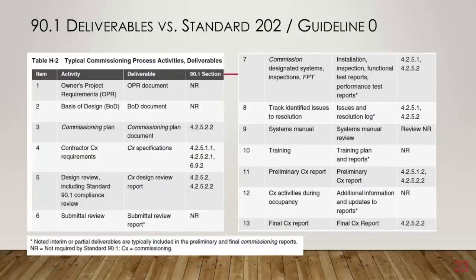Now this table is taken from the informative appendix. Again, what we did our best to do in that informative appendix is walk through, here's the standard process that Standard 202 lays out and indicate where 90.1 specifically requires those things and point to the actual sections in 90.1 where those requirements are made. Now you notice, for instance, we don't require in 90.1 an OPR document or a basis of design document. From 90.1's point of view, the 90.1 standard is that document as far as we are concerned. Now we do in the informative appendix say that there are probably great benefits to including those things in your commissioning process.